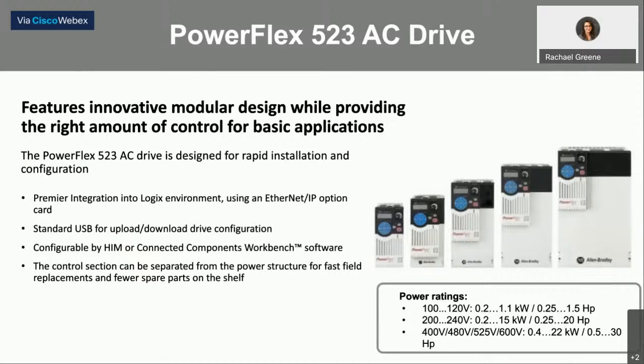No worries. So the 520, all the 520 series drives have the ability to be configured offline, meaning that say a maintenance guy can be installing the power structure out in the field, and an engineer can plug into the control module of the drive and program it via just a USB printer cable. This drive is easily programmed using the free Connected Components Workbench software that Rockwell offers to everyone. It's an unlicensed software, and it talks to all PowerFlex drives, from the low voltage drives as we're talking about here and the medium voltage.